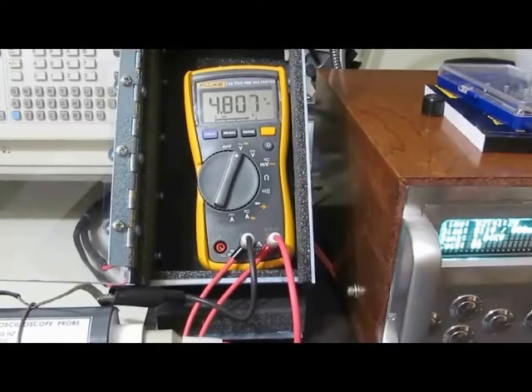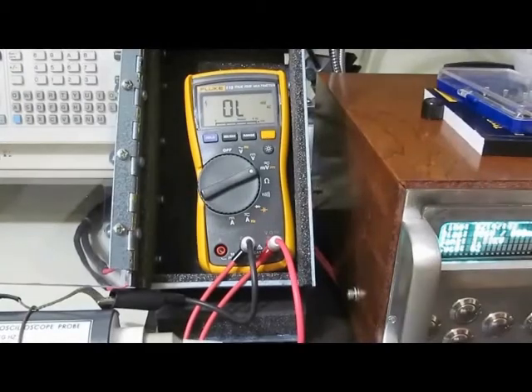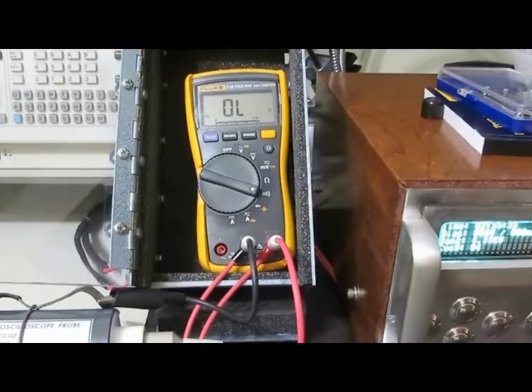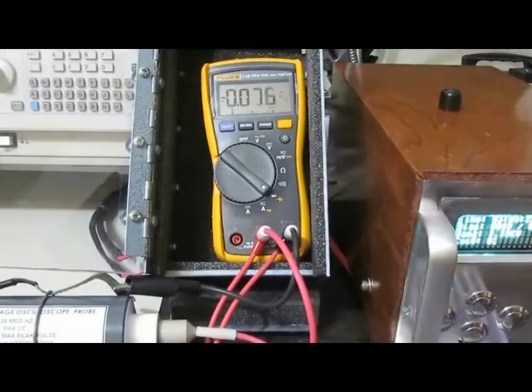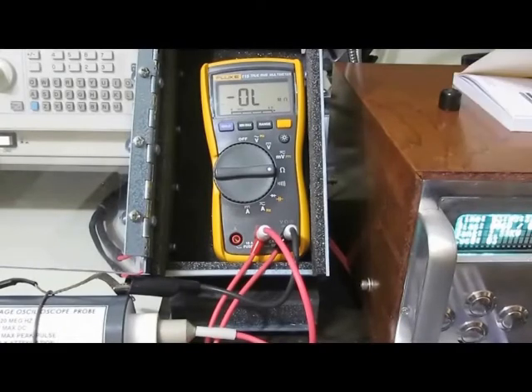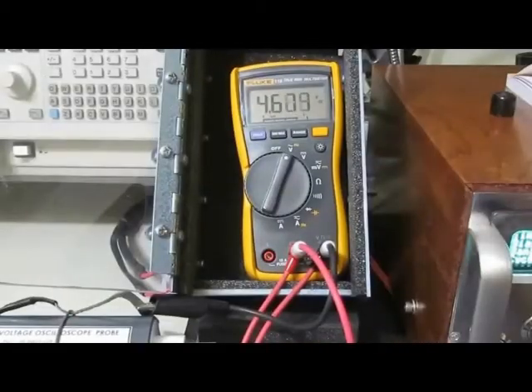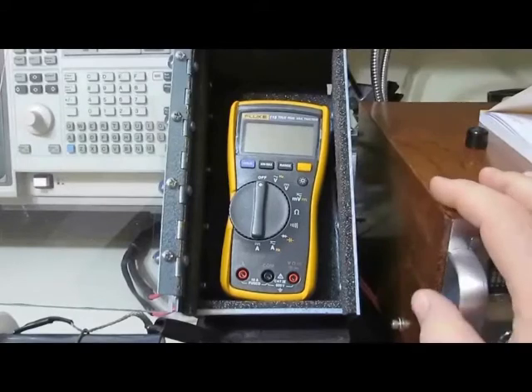This will be with the new generator set at its max settings. It's roughly 5.9 kV. That's it. We'll go ahead and functional test. So that's all the testing I can do with this generator.